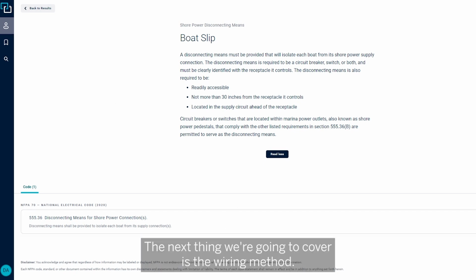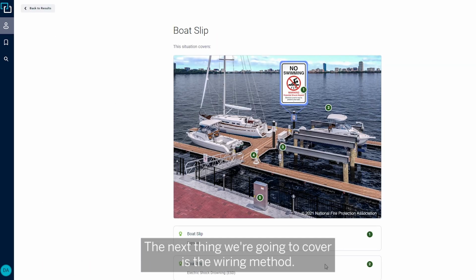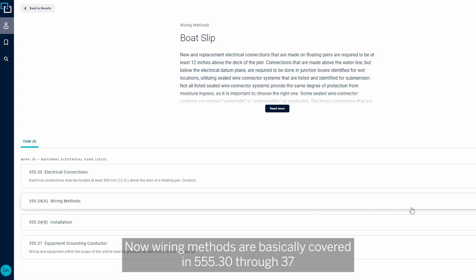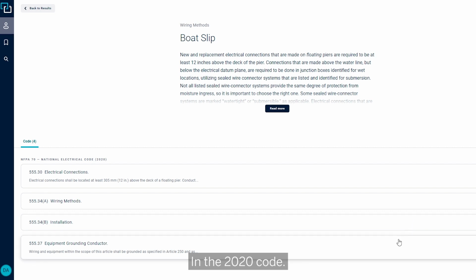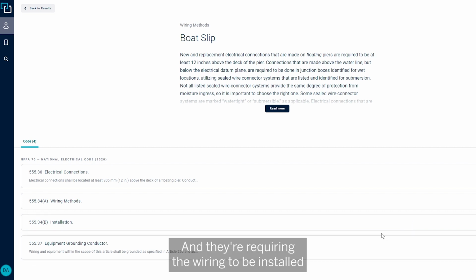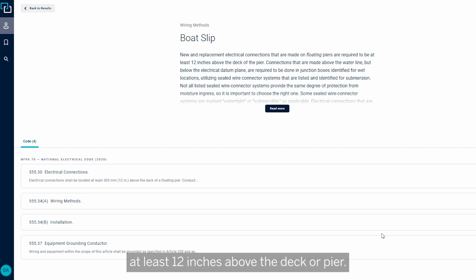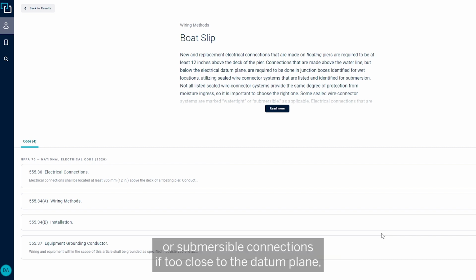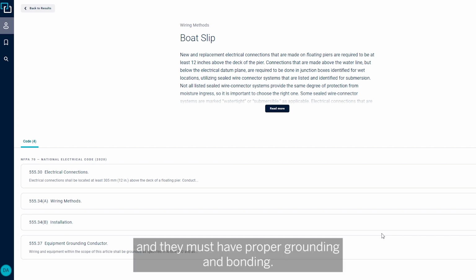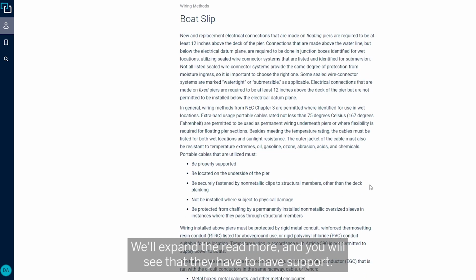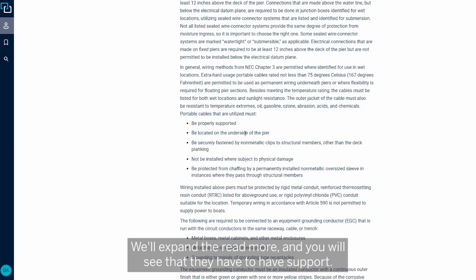The next thing we're going to cover is the wiring methods. Wiring methods are covered in 555.30 through 37 in the 2020 code, and they require the wiring to be installed at least 12 inches above the deck or pier. They may need to utilize watertight or submersible connections if too close to the datum plane, and they must have proper grounding and bonding. We'll expand the read more, and you will see that they have to have support.